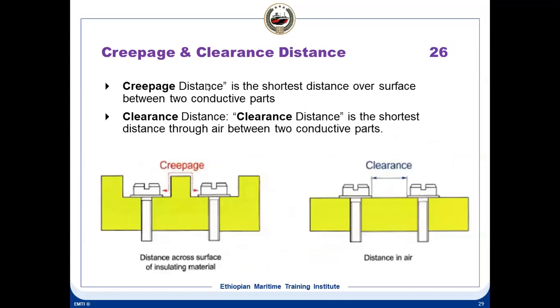Creepage distance is the shortest distance over the surface between two conductive parts. This is the insulator part, and these two are conductive parts. This distance is called creepage. Clearance is the shortest distance through the air between the two conductive parts. So this is known as the clearance. Clearance and creepage: creepage is the distance over the surface between two conductive parts, and this is the air clearance.